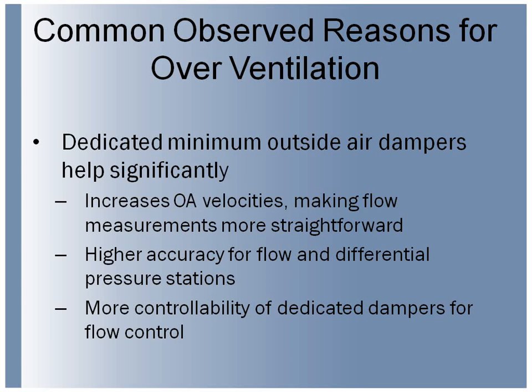So having a small dedicated minimum outside air section that's always open and then a large economizing section that is only open during economizing mode can really have a huge impact on our ability to take these measurements. So it increases the velocities across that damper, which makes it easier to get more precise and accurate measurements. It makes it easier for the flow stations, if you're going to use that, or some type of differential pressure control to work. And we have more controllability of separate dampers now as opposed to one damper bank.